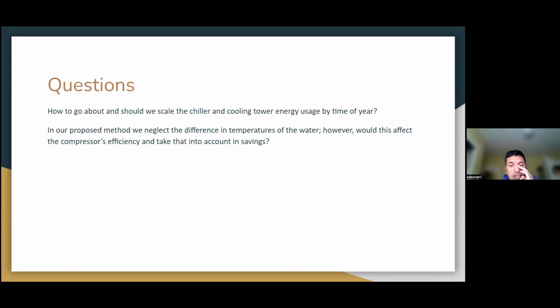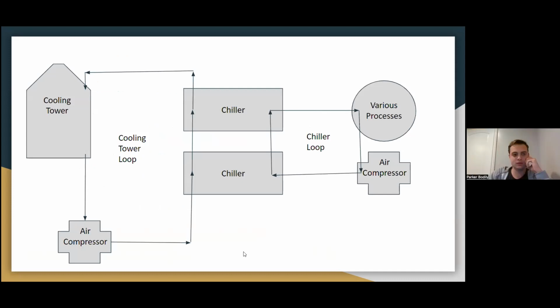Okay. How would we go about this? First, let me give you two quick rules of thumb. Go back to your chiller drawing. This one? Yeah. On your chiller loop, 2.4 GPM equals 1 ton of cooling. Rule of thumb. A chiller will chill 2.4 GPM per ton.